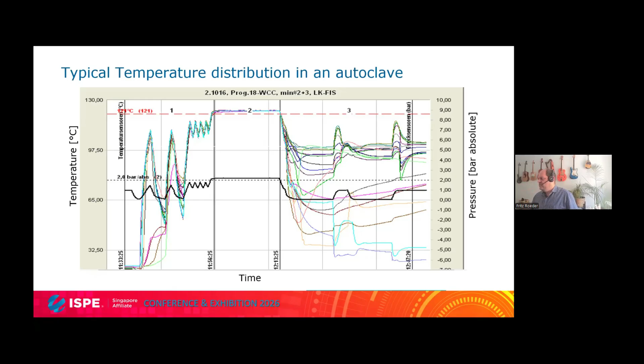All the others show the temperature distribution, and once you reach the 121, the clock starts ticking. You need to wait for 15 minutes before you release the chamber, bring down the pressure and the heat again, and this is what it looks like. And like this, you also define the cold spot. The sensor with the lowest temperature is your worst case point, and this is where you later place your monitoring sensor for the routine. This is how it goes. Good, so much about sterilization.